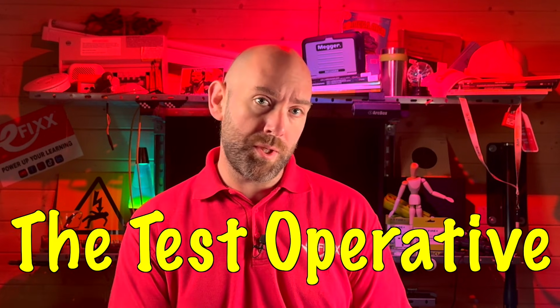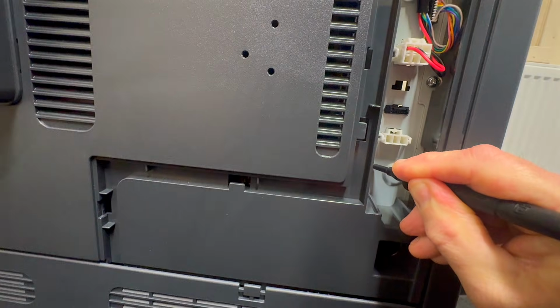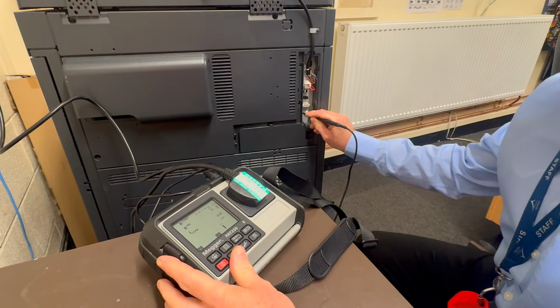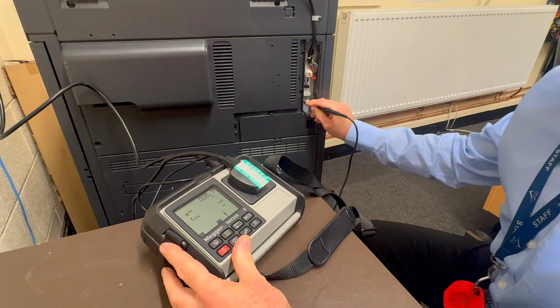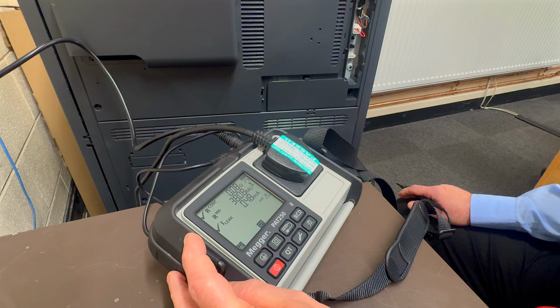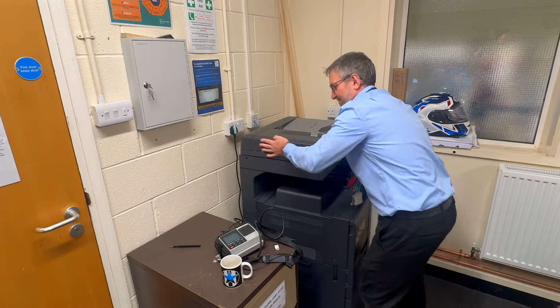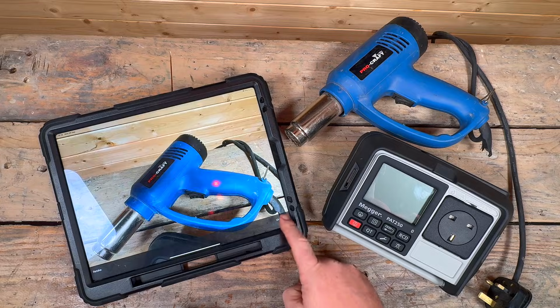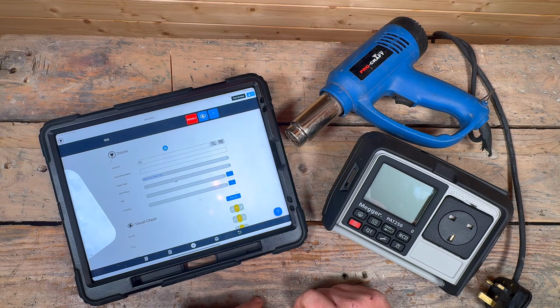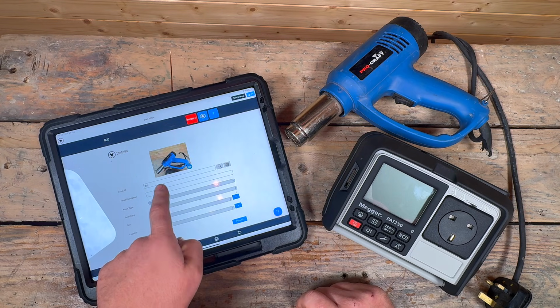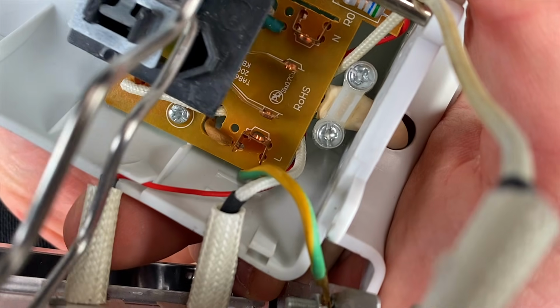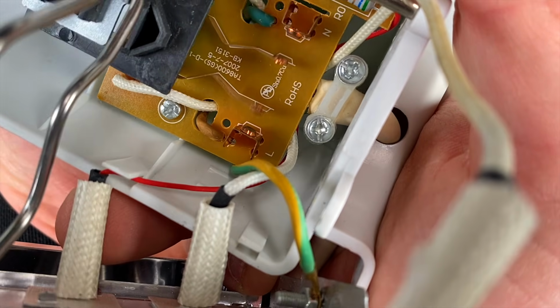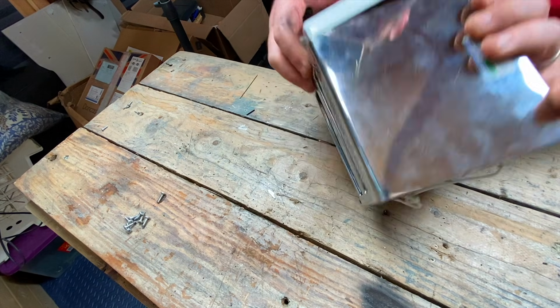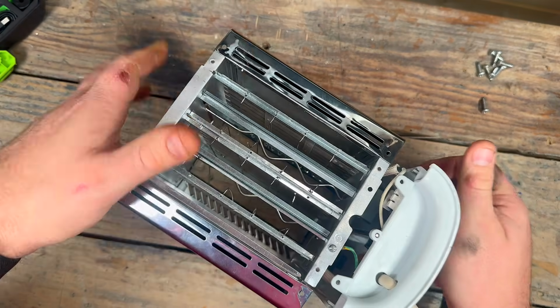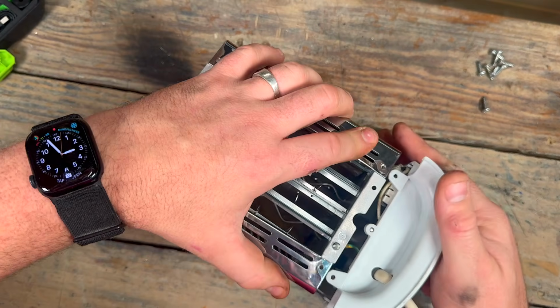Then we have the test operative. This is the person who performs the combined inspection and test described in the code. They must carry out electrical tests, interpret the results correctly, and decide whether the equipment is safe for continued use. Training and experience is essential. The test operative must also complete the records accurately and sign them off, as their signature confirms the final judgment. There is also the person who repairs the faulty equipment. They must be competent to work safely on the type of equipment being repaired, understand the hazards associated with reassembly, and make sure the equipment is safe before it goes back into service.